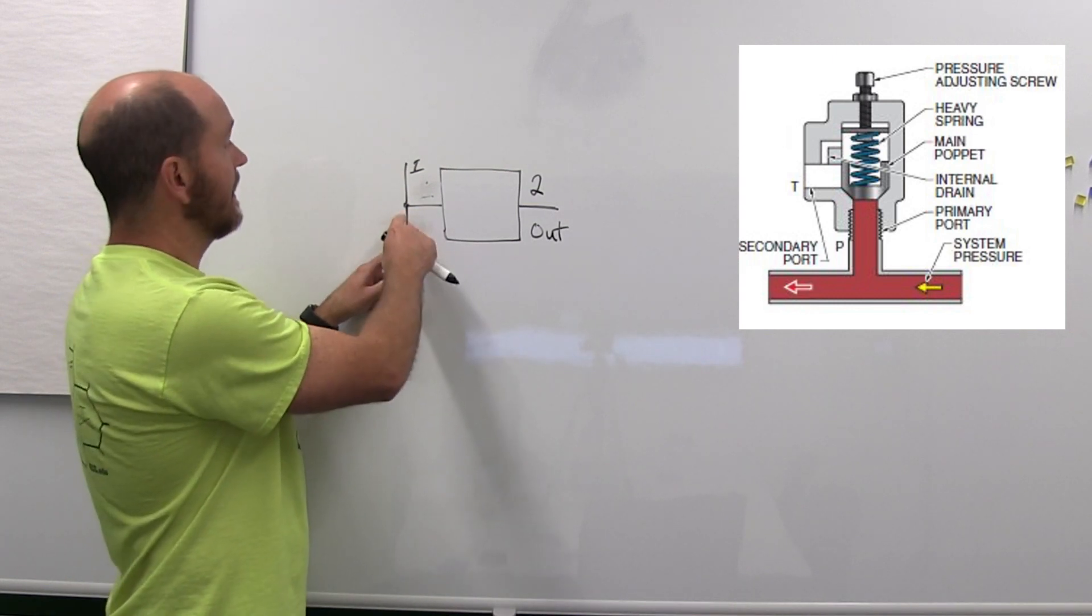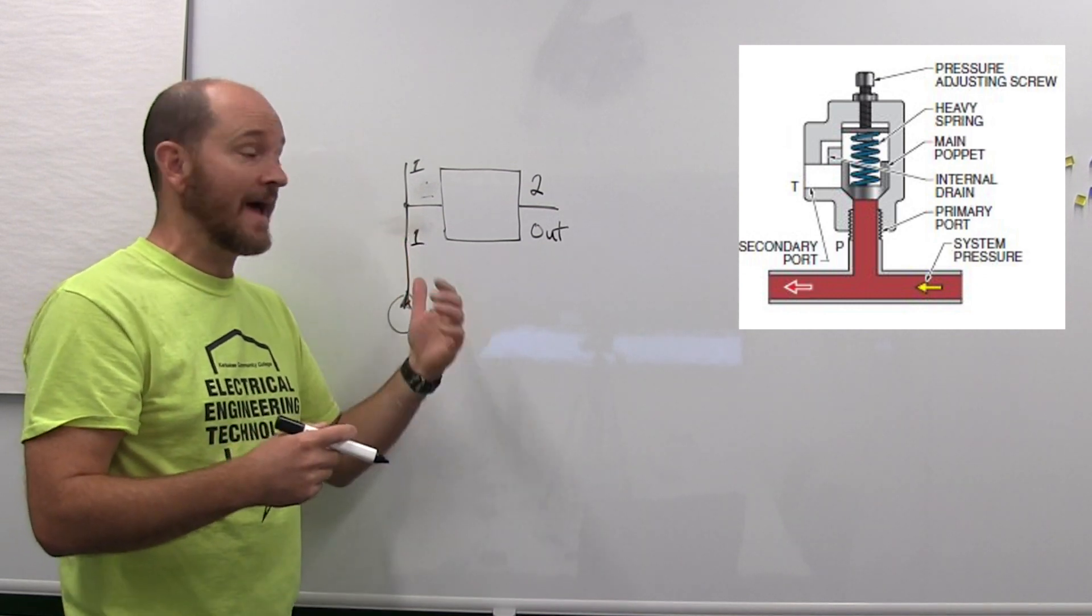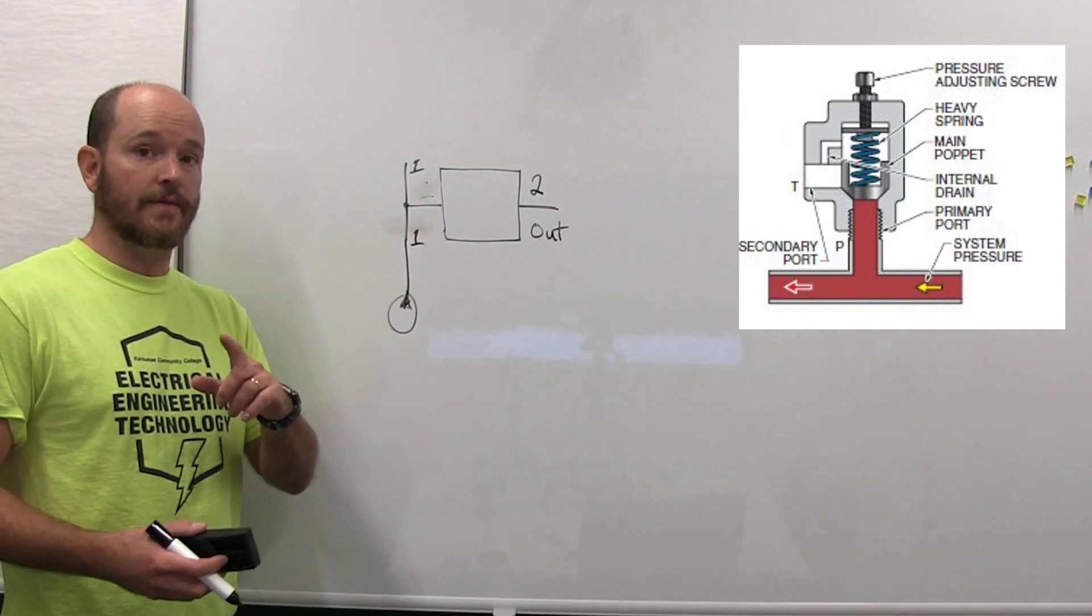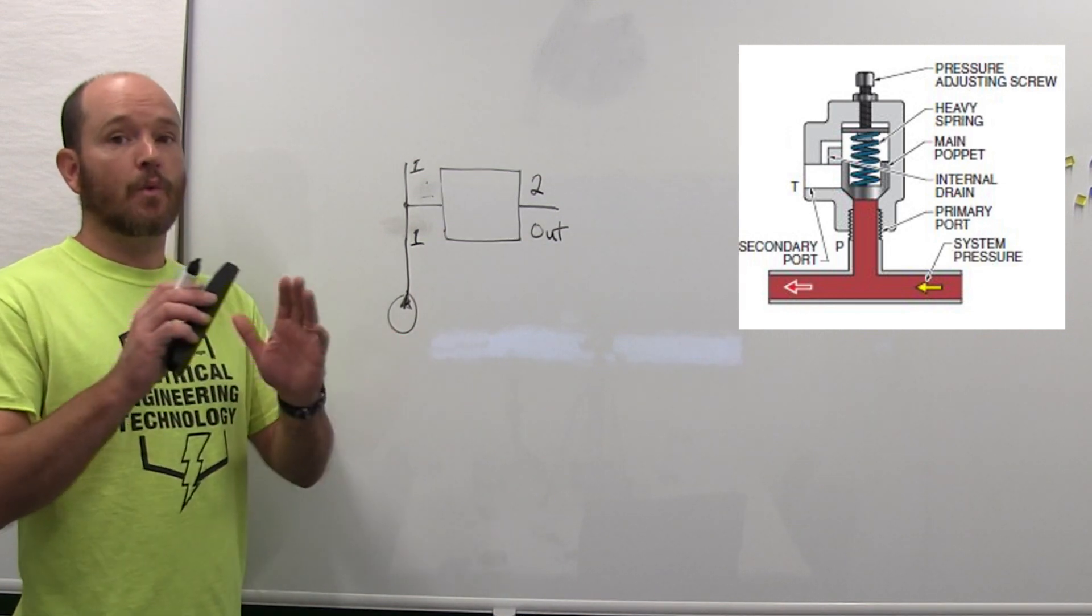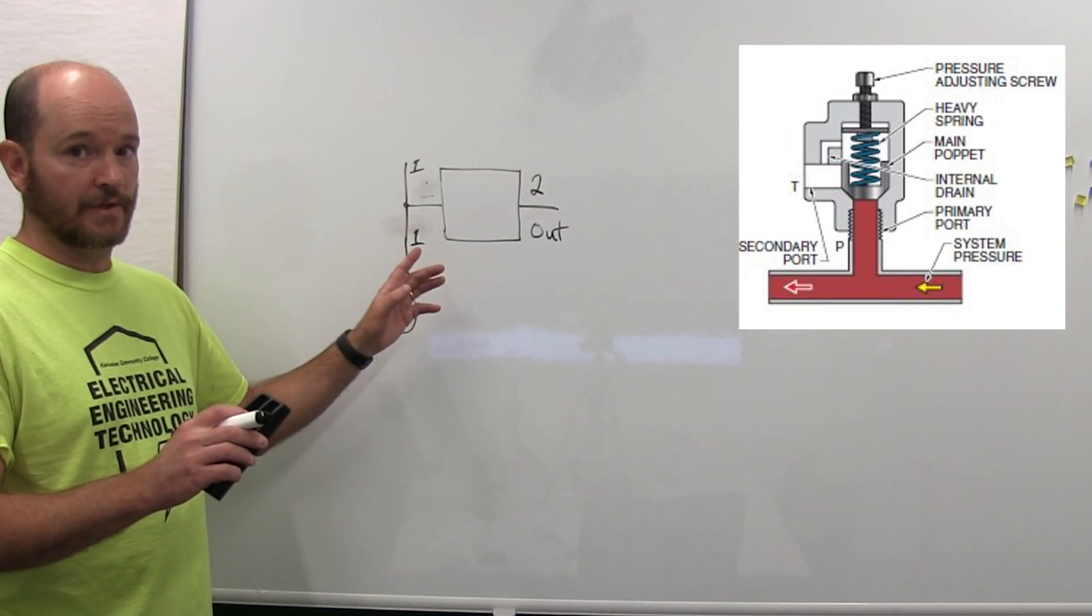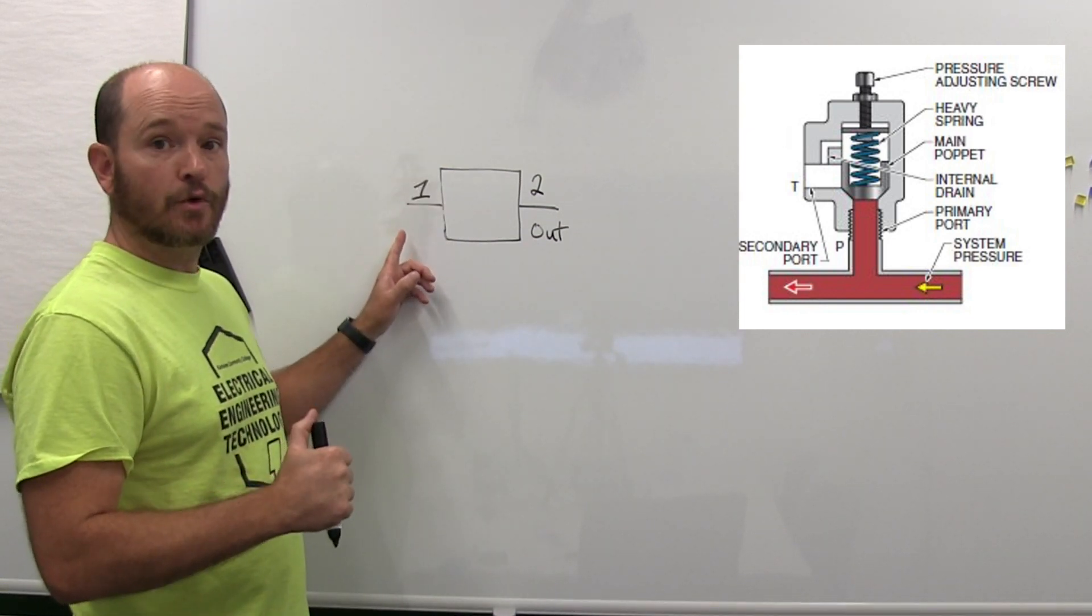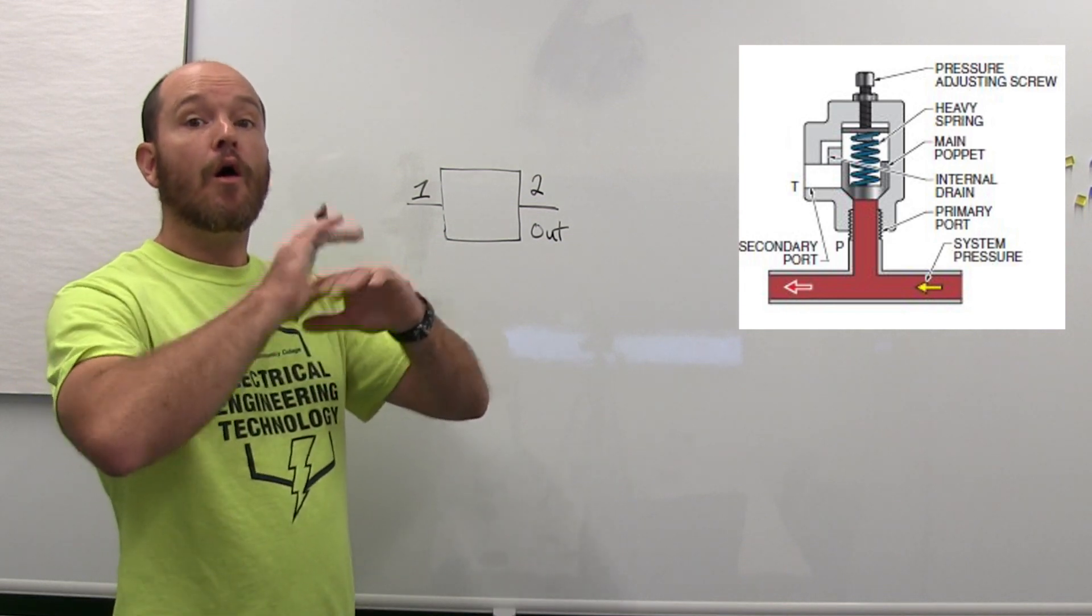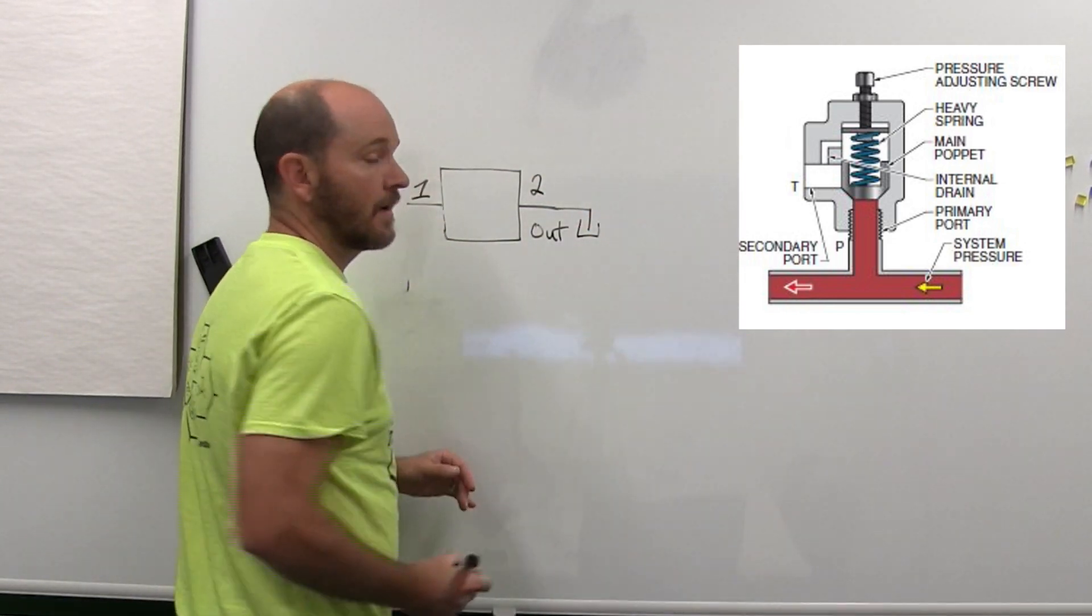If that's the case, this has a built-in T. Oil typically comes directly from the pump into one of the port ones and out the other port one. Other times there is an external T that is located there, so you have to compare the schematic diagram to the real world to know if the T is built into the relief valve or external.